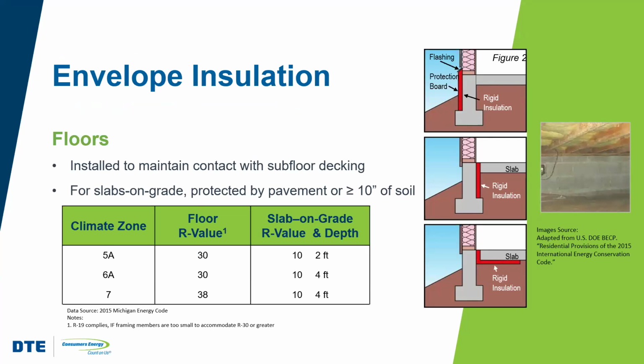Floors can account for 25 to about 30% of the building envelope surface area. And when defects in the air barrier and insulation system exist, heat is lost through the floors over unconditioned basements and vented crawl spaces. This can cause cold floors, which we know are not comfortable, and it can increase heating and cooling costs. So a good design will make sure floor insulation is in full contact with the subfloor air barrier. The insulation will be installed in the floor joist bays without misalignment, without compression, without gaps or voids. And if necessary, there may be some supports like metal staves or netting to help keep that insulation in permanent contact with that air barrier above.